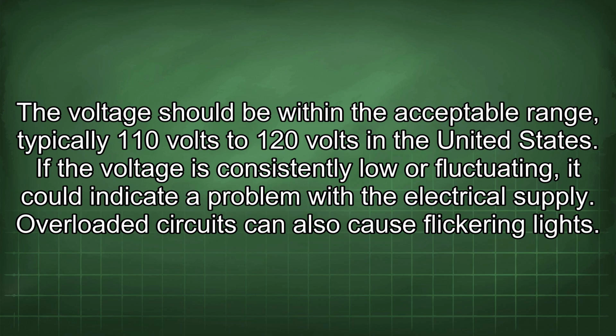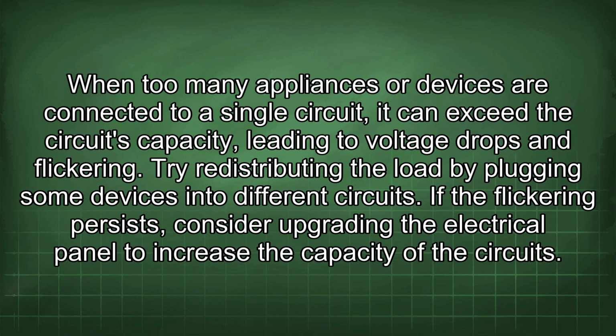Overloaded circuits can also cause flickering lights. When too many appliances or devices are connected to a single circuit, it can exceed the circuit's capacity, leading to voltage drops and flickering. Try redistributing the load by plugging some devices into different circuits. If the flickering persists, consider upgrading the electrical panel to increase the capacity of the circuits.